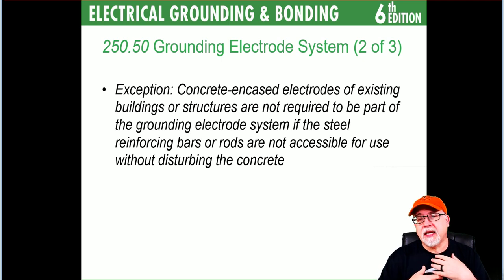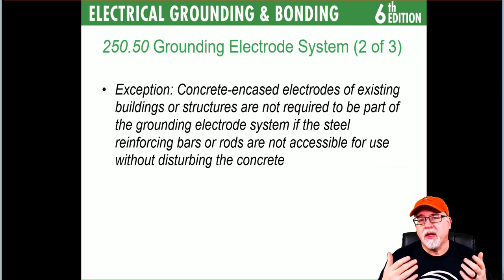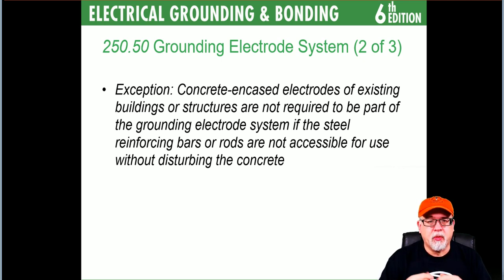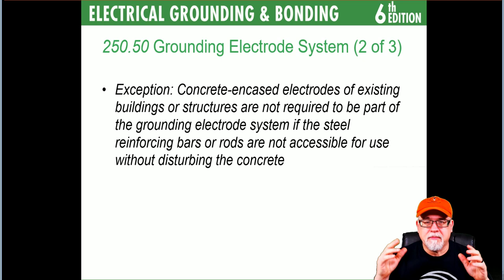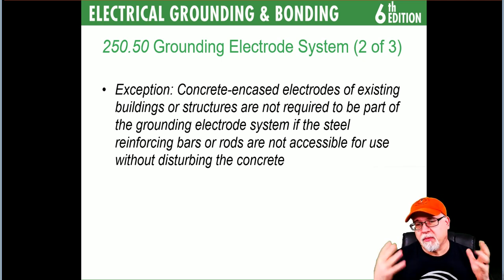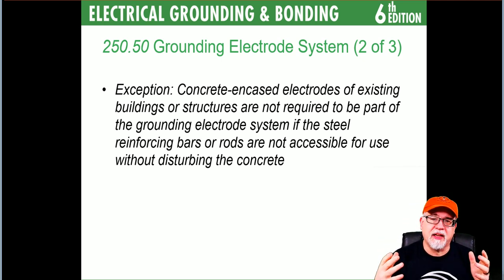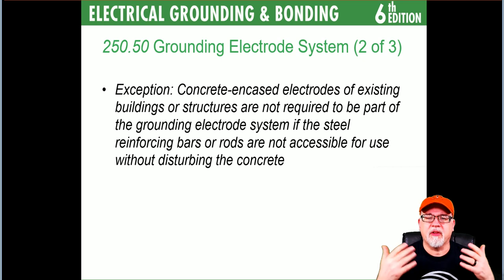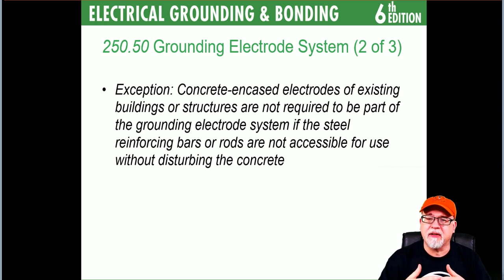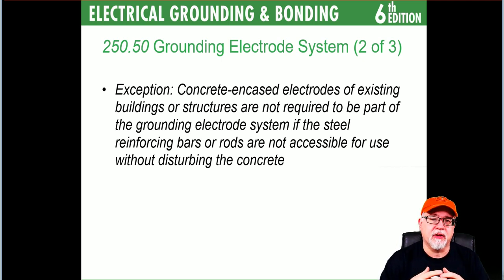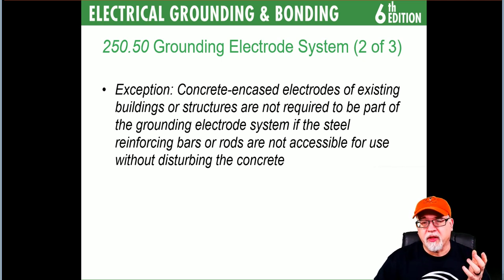We used to use the term 'all electrodes available'; now we use 'all that are present.' If a concrete encased electrode is already in the slab and the only way to connect to it would be to chisel it up, then you treat it as not present and install a grounding electrode system accordingly — you wouldn't install the concrete encased electrode option in that case.